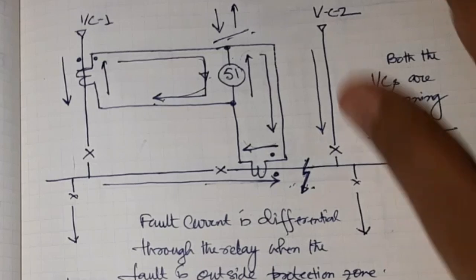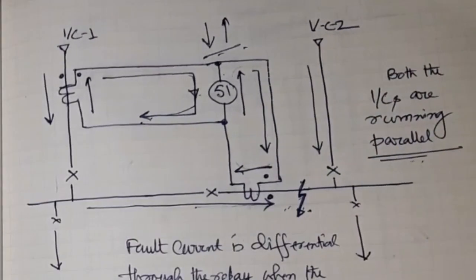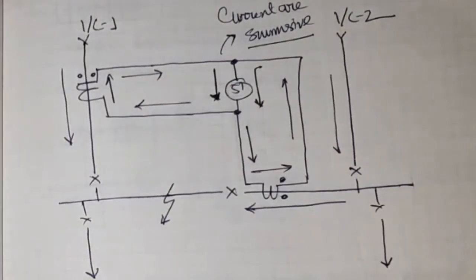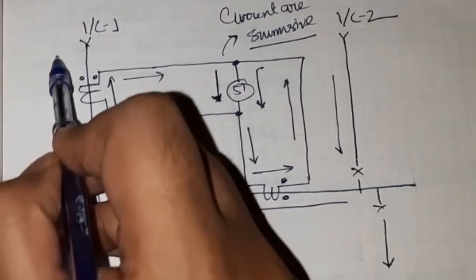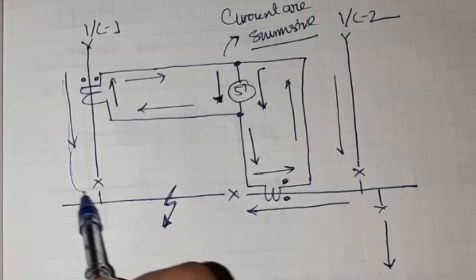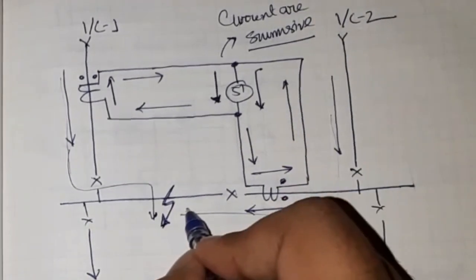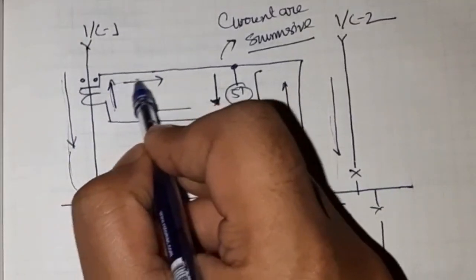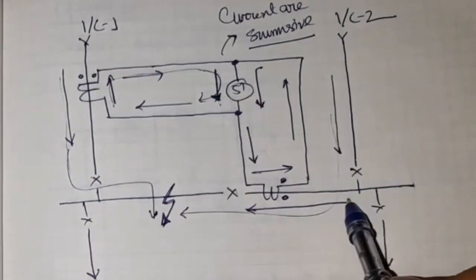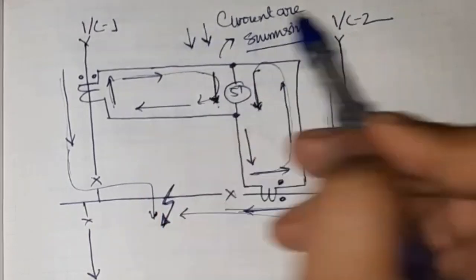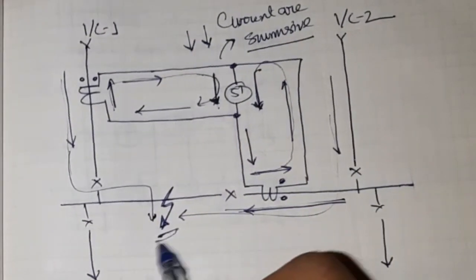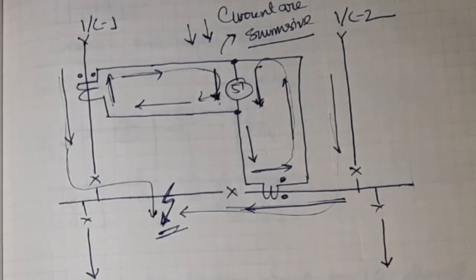Now we will see what happens for a fault inside the protection zone. When there is a fault inside the protection zone, the current from Incomer 1 flows downward and from Incomer 2 also flows downward — both currents are additive. So for a fault inside the protection zone the relay sees a higher summation current, and for a fault outside the zone the relay sees a lower differential current. Therefore the relay will pick up for a fault inside the protection zone.